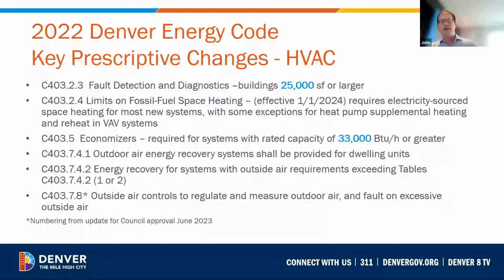Economizers. For airside economizers common on many rooftop systems, the requirement has been extended for smaller systems. So now any systems with a capacity of 33,000 BTUs or greater require airside economizers. This effectively sets a requirement for systems with a nominal cooling capacity of 3 tons or greater. There are energy recovery requirements for systems with outside air ventilation rate exceeding minimum thresholds. When required, there are also limits on the pressure drop across the energy recovery device, as well as supply fan efficiency requirements for that energy recovery system fan.